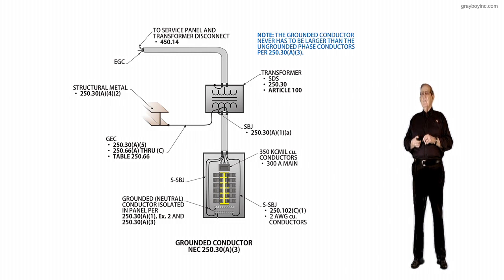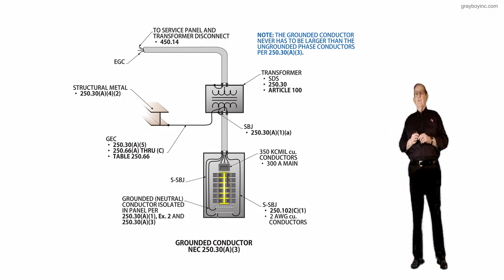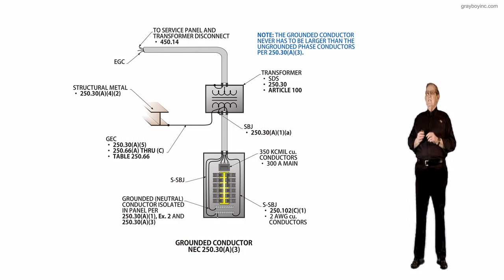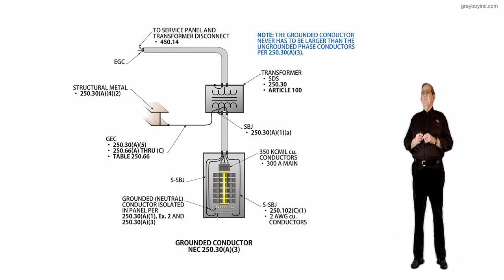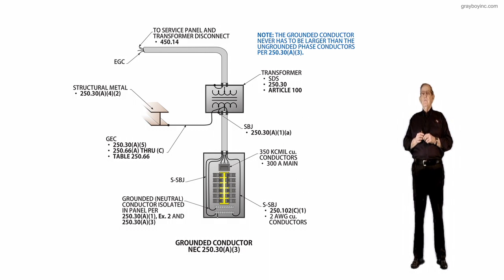And then the reminder is that the grounded conductor, to carry fault current or short circuit current, has to be at least the size from Table 250.102(C)(1), and then calculate it as a neutral carrying conductor by 220.61 and use the larger of the two. And that pretty well summarizes what this new sentence is trying to point out in the purpose of change.